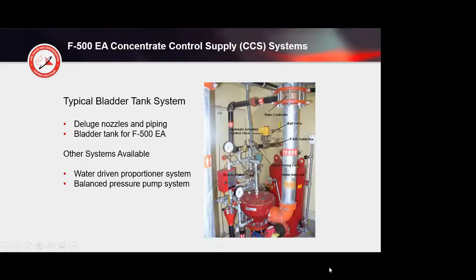So looking at it in real time, this is the bladder tank in the back here. This is your deluge valve. So the water is coming up from here and then going here up to some hazard. This probably, based on the size of the tank, is probably protecting a Class A because it's a smaller tank. We're probably proportioning at 1% for Class A. I would suggest this is probably protecting a conveyor belt that handles coal at a power plant.